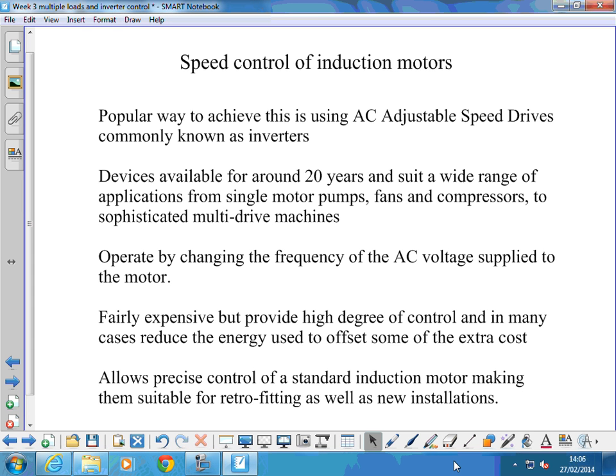A popular way to achieve speed control with these motors is to use AC adjustable speed drives, or commonly known in the trade as inverters. These devices have been available for around 20 years and they suit a wide range of applications, from single motor pumps, fans, compressors, to sophisticated machines with multiple drives. So they are very flexible. They operate by changing the frequency of the AC source voltage that we supply to the motor. So they take the AC three-phase supply, or in some cases a single-phase supply, and convert it into a variable frequency AC supply.